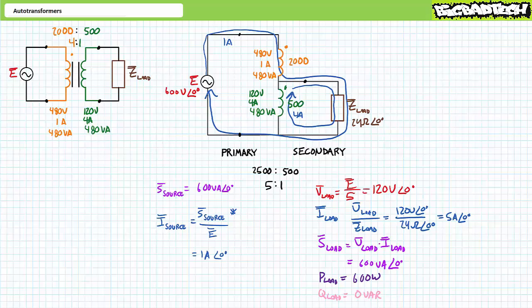Consider the amount of power capable of being transferred by these same windings configured as an auto transformer. When configured as a traditional transformer, it only had a rating of 480 volt amperes. However, when configured as a step-down auto transformer, it allows the same device to transfer 600 volt amperes — an increase of 1.25 times — without ever exceeding the rating of either winding.